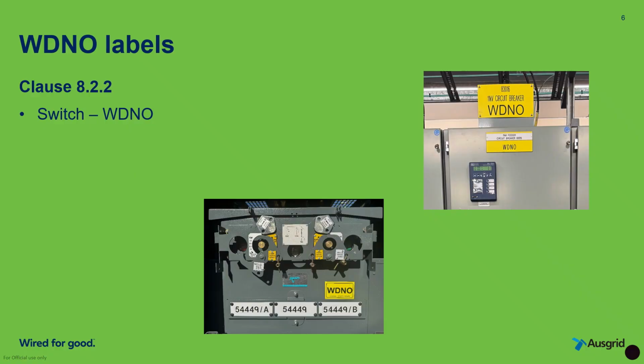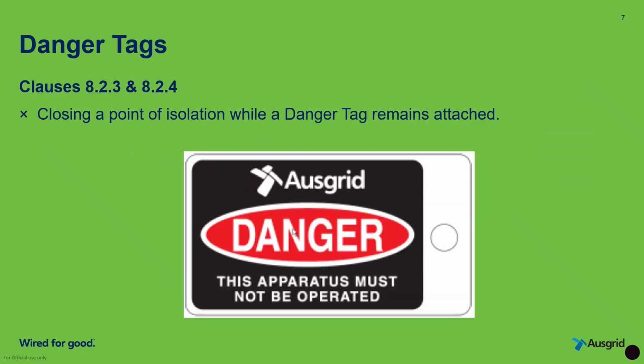The requirements and reasons for a switch to be labelled "warning do not operate" or "WDNO" have been clarified. In addition to the would know label, if a switch cannot be safely closed due to the mains and apparatus that are or are not connected to the switch, an operator's danger tag must also be attached to the switch. Clauses 8.2.3 and 8.2.4 now clearly prohibit any person from closing a point of isolation while a danger tag remains attached to the point of isolation. This is the intent of the words, "This apparatus must not be operated," that are displayed on the danger tag.